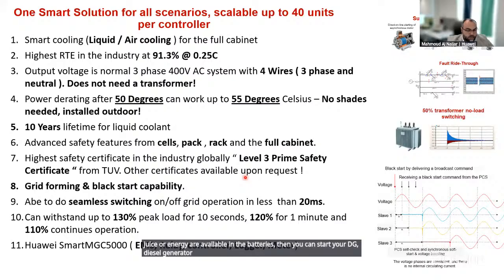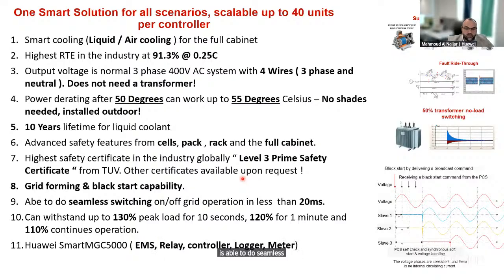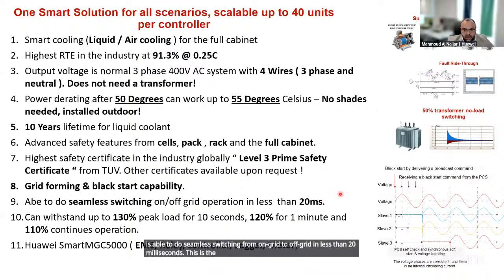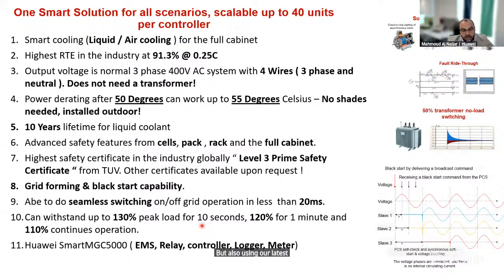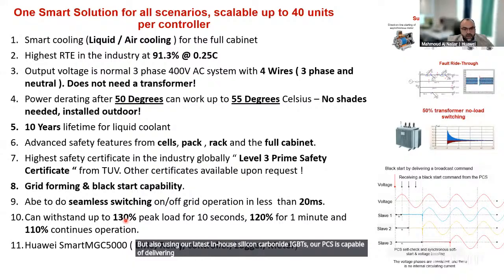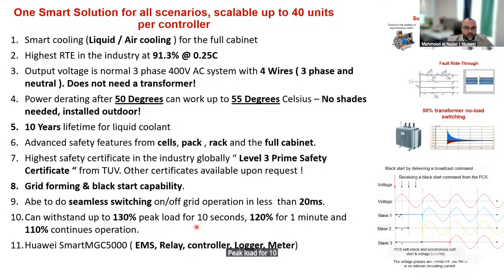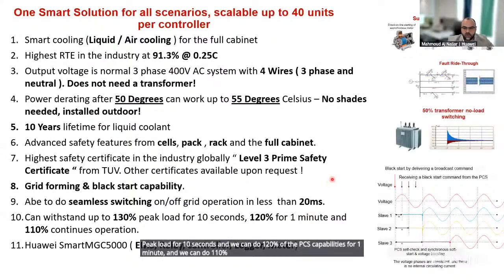This solution is able to do seamless switching from on-grid to off-grid in less than 20 milliseconds. This is the highest in the industry, almost reaching UPS level of switching time. Also, using our latest in-house silicon carbide IGBTs, our PCS is capable of delivering 130% peak load for 10 seconds, and we can do 120% of the PCS capability for 1 minute, and we can do 110% continuous operation of the PCS.